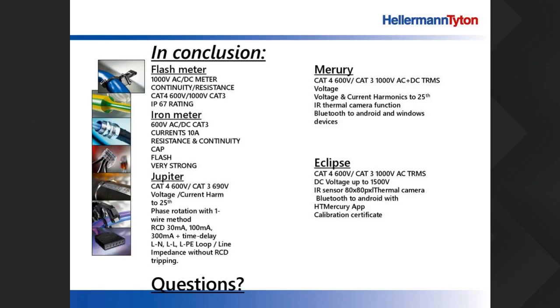It's got a Cat4 600 volt rating. It measures voltage and current harmonics. It allows you to do phase rotation with one wire method. The RCD function allows you to measure 30 milliamp, 100 milliamp, and 300 milliamp earth leakages with a time delay. The L-PE loop measures between live and neutral, live to live, live to earth, and measured from a plug point. Will not trip your earth leakage.